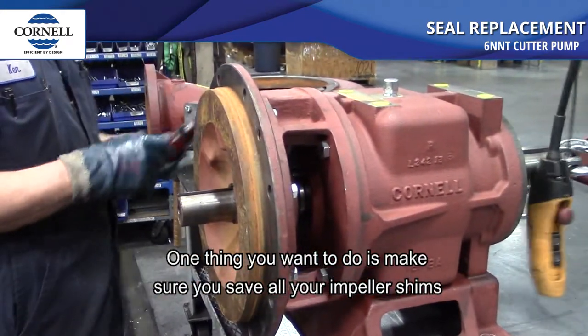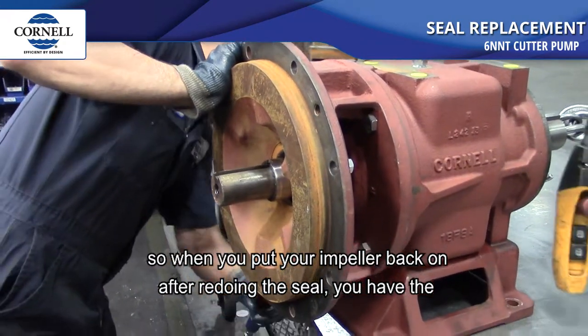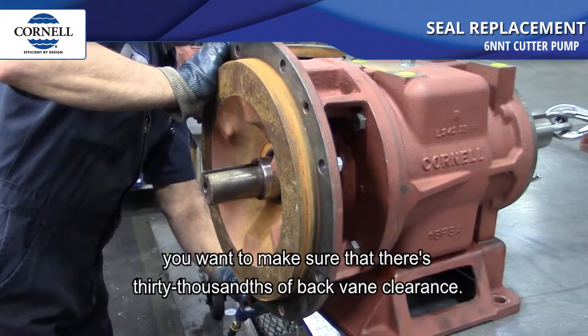One thing you want to do is make sure you save all your impeller shims so when you put your impeller back on after redoing the seal you have the proper shimming. Also, when you put the impeller back on you want to make sure there's 30 thousandths of back vane clearance.